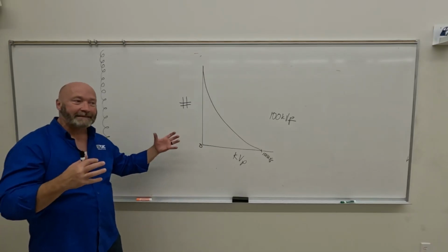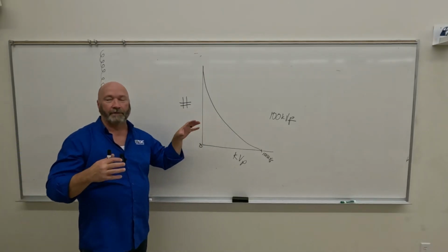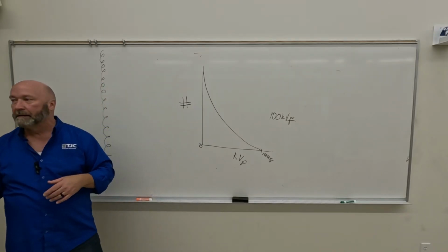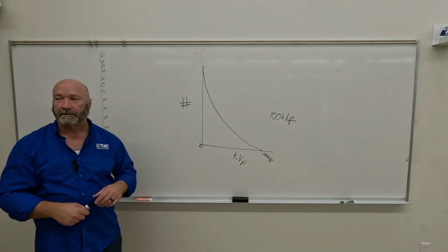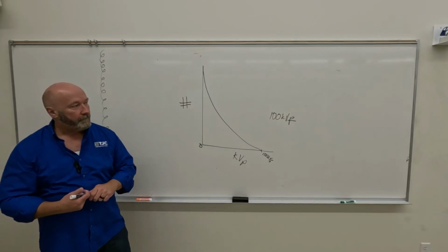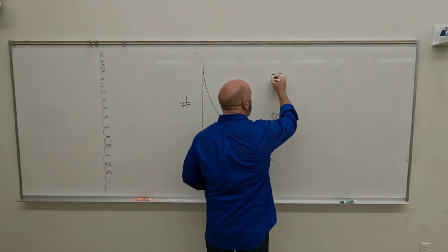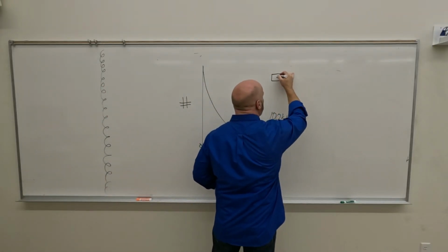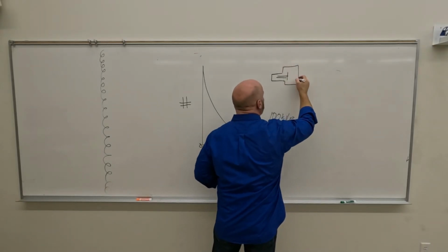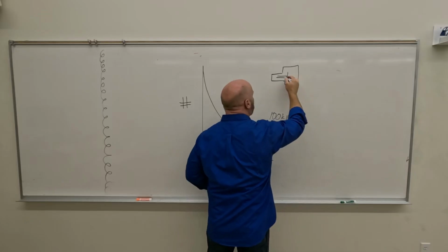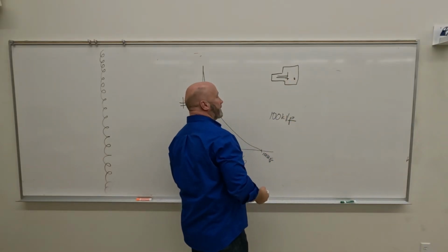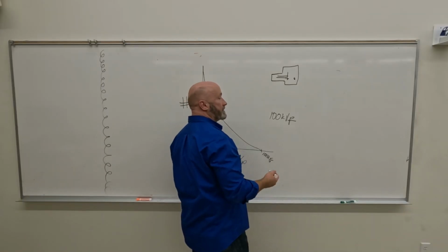Okay, but this is where you're inside the X-ray tube, right? It hadn't even gotten to the glass. You're inside the X-ray tube. This is the face of the target. That's what it looks like. But you've got the X-ray tube, right? You've got anode, and you've got cathode, right? The X-rays are created right there. What's it going to hit before it exits the protective housing?